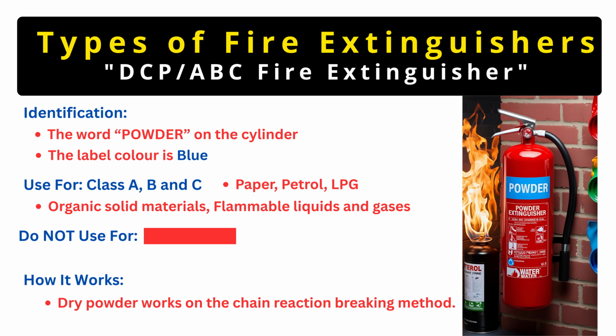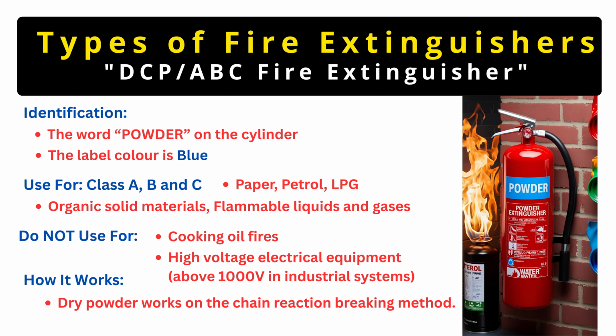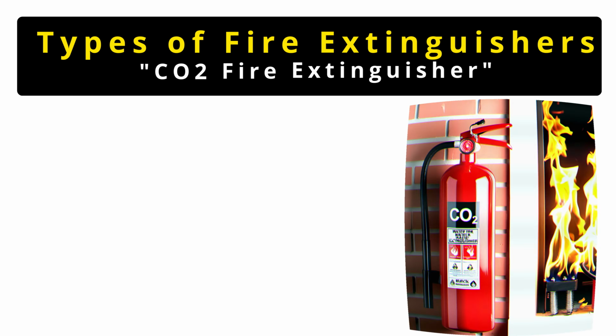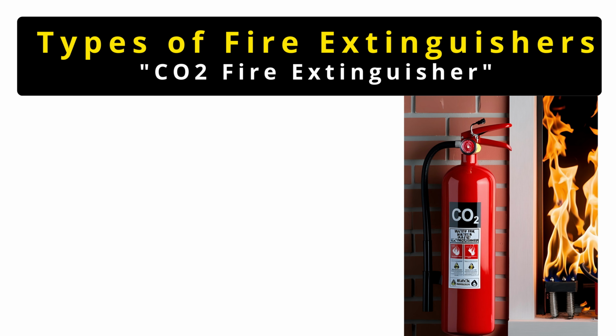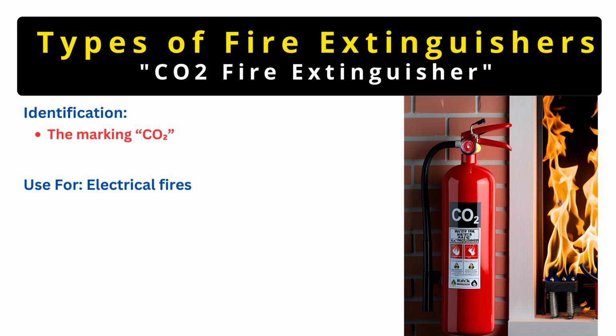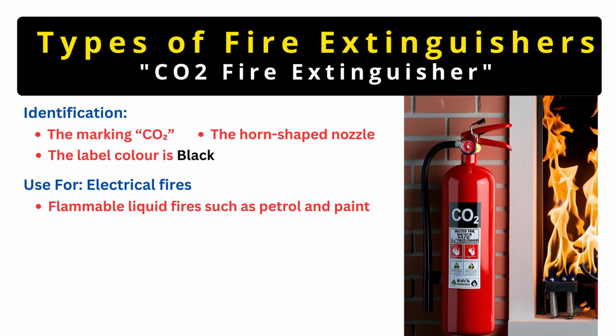Dry powder extinguishers should not be used for cooking oil fires or high voltage electrical equipment above 1000 volts in industrial systems. Also, dry powder causes heavy dust contamination, so it is not suitable for server rooms and clean environments. Now let us understand the carbon dioxide fire extinguisher, also known as CO2 extinguisher. CO2 extinguishers are predominantly used for electrical fires and are commonly installed in server rooms, control rooms, electrical panels, data centers. CO2 extinguishers can be identified by the marking CO2. The label color is black, with a horn shaped nozzle. CO2 extinguishers are used for electrical fires and flammable liquid fires such as petrol and paint.